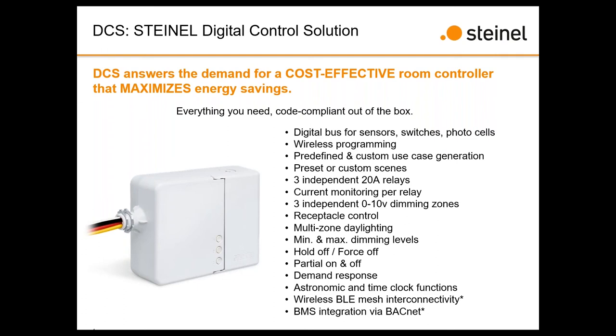The first one is, does the current monitoring function provide reading of actual value in amps? I'll take that one. It does. It shows you the amperage on relay 1, relay 2 and 3. You have to put what the voltage is, but it'll automatically read it on relay 1, and then it shows the amps and the watts, and it does a few other calculations there for you also if you select them.